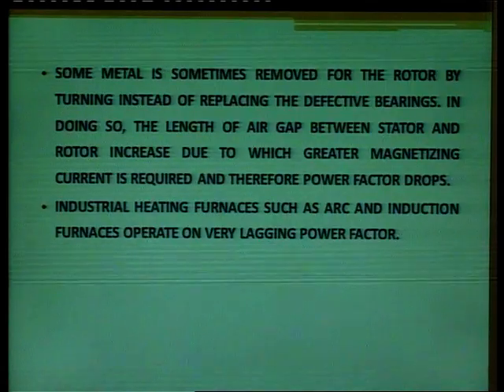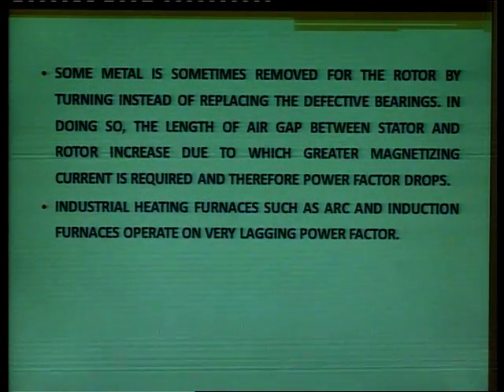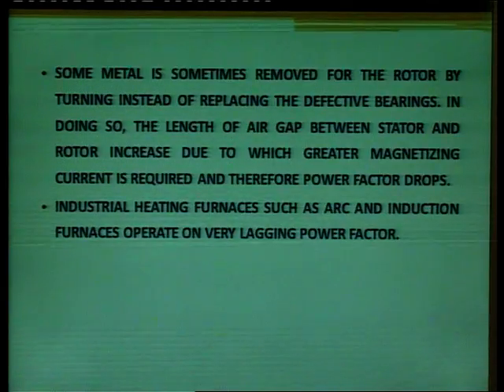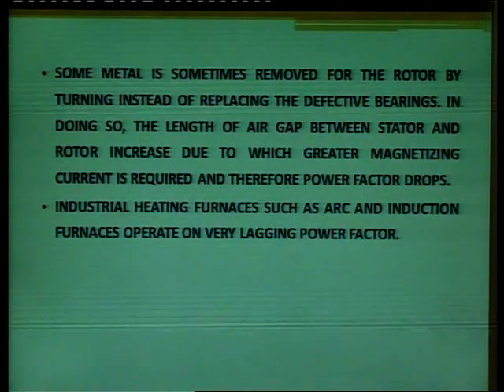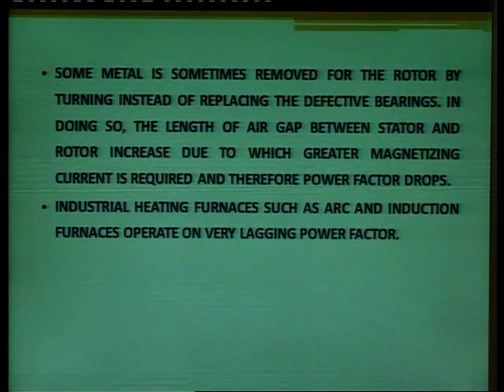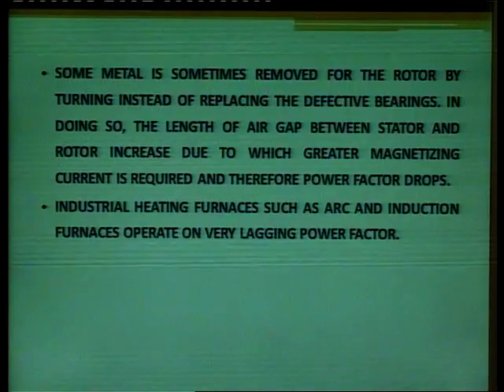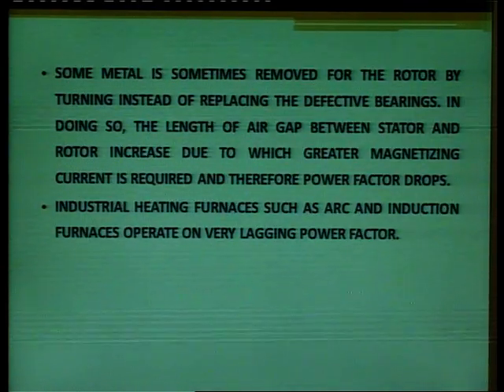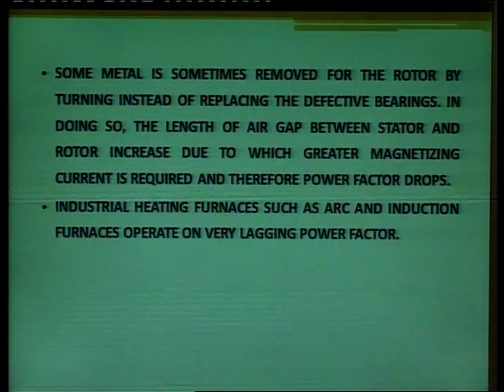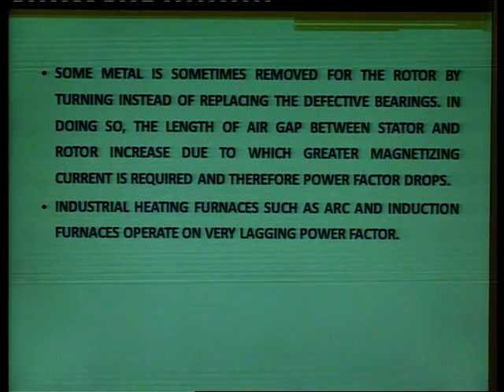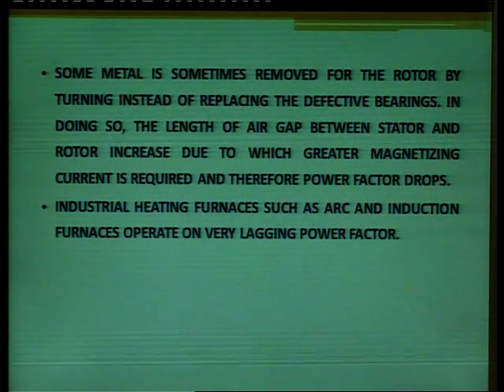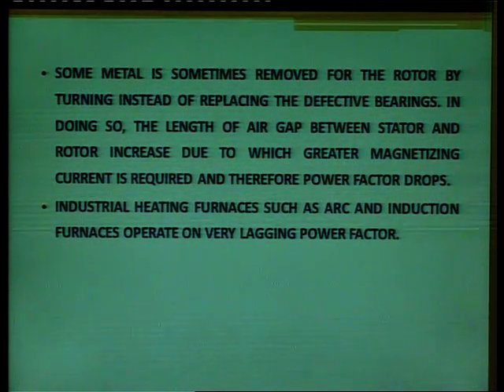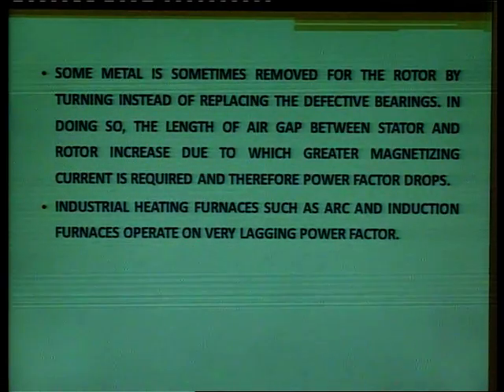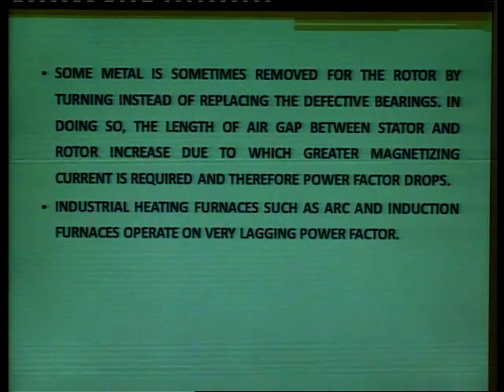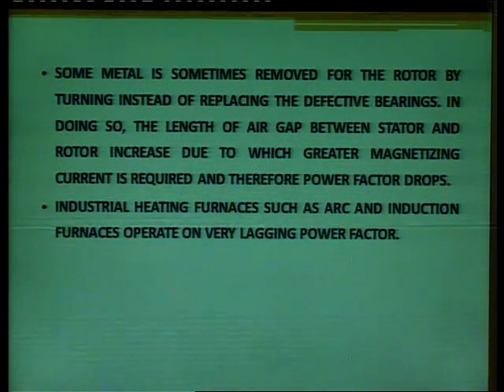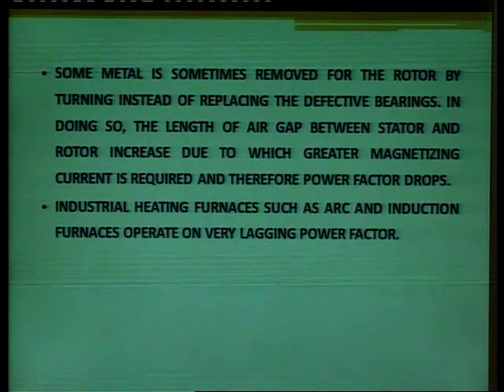So try to replace your motor if it is demanding some repair or is worn out; then it should be repaired by a proper factory mechanic. So try to see the air gap between the rotor and stator. If the air gap is more, then the power factor is low and lagging. So these are the factors. Next, industrial heating furnaces such as arc and induction furnaces operate on a very lagging power factor. So arc furnaces are also one of the reasons for making the power factor low and lagging.